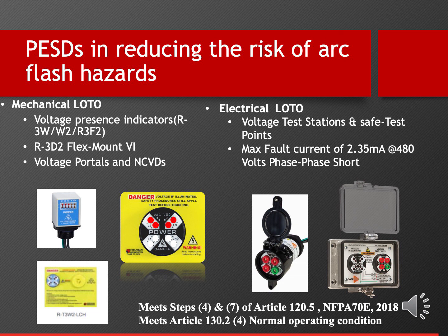You can perform this live-dead-live test under normal operation when the doors are closed and secured, which meets article 120.5 step 4. These devices are built with high impedance protected circuitry, which limits the maximum fault current to 2.35 milliamps at 480 volts when any two test point jacks are shorted together.